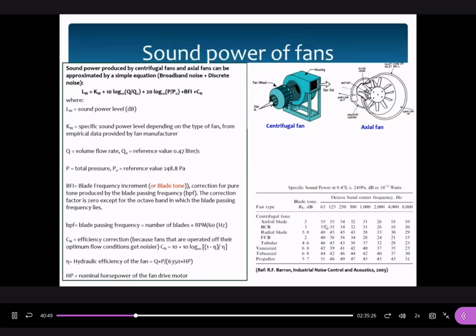You may ask why we use 0.47 liters per second or 248.8 Pascal as references, rather than other values. It's because the test was conducted according to the US system. Originally, 0.47 liters per second equals 1 cubic foot per minute, and that was one of the two reference conditions used. The second condition, 248.8 Pascal, is exactly equal to the pressure under 1 inch of water column.